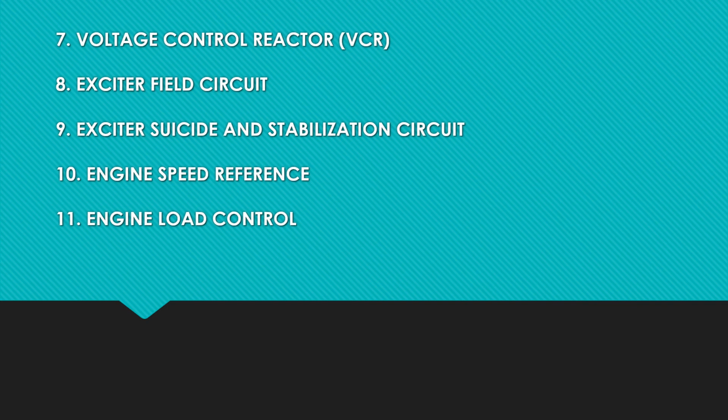This DC current in PWM winding affects the current in the AC winding in such a way that it causes the transistor EFT to switch off and cut off current in exciter field. Diodes XD18, XD19, XD20 and XD21 clamp the voltage across PWM winding to approximately 1.5 volts in both directions. Capacitors EC1 and EC2 are used to stabilize the exciter during motoring operation with EC1 capacitor disconnected above notch 3.